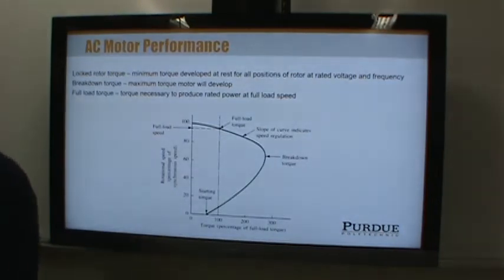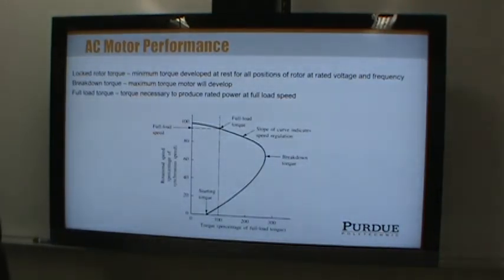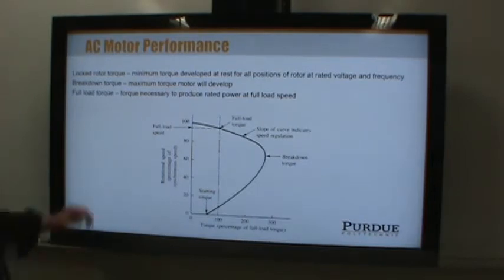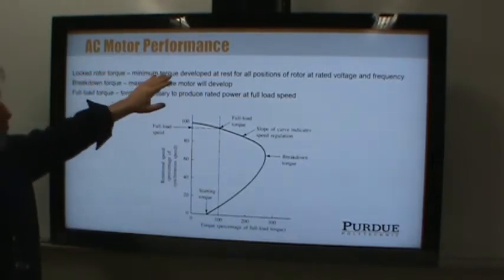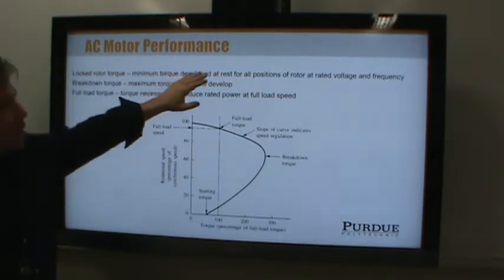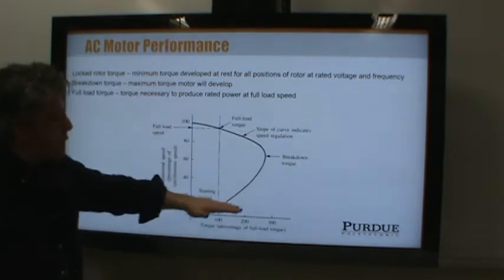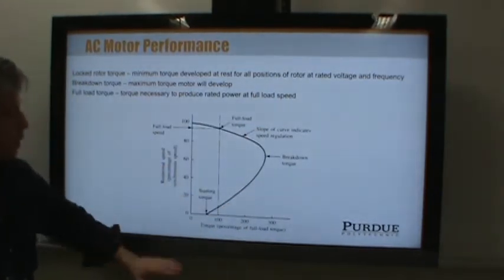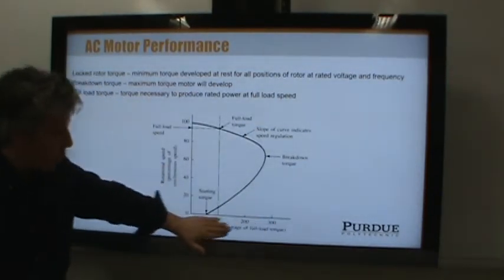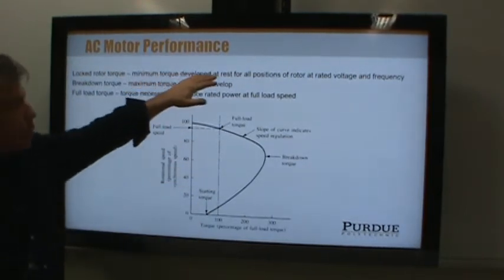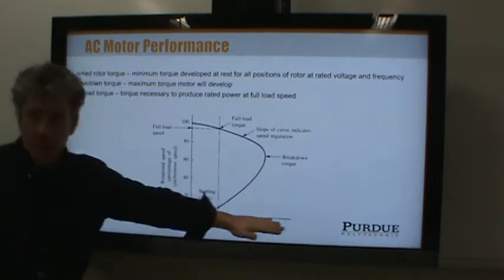What we care more about is the performance of motors. Here's a typical torque-speed curve for an AC motor, and there are some interesting points. We'll start with the locked rotor torque — this is the minimum torque developed at rest for all rotor positions at rated voltage and frequency. This curve has torque on one axis and rotational speed on the other, so we're looking at the at-rest condition.